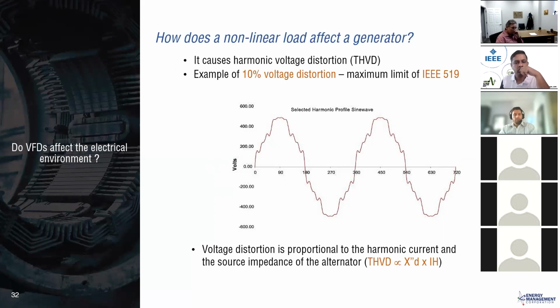This is the most important point that I want to focus on, because we can see that the distortion is directly proportional to the source impedance as well as the harmonic current. We have two solutions that we can propose. The first solution is having a good filtration device and/or reducing source impedance, or in other words, just having a large alternator.